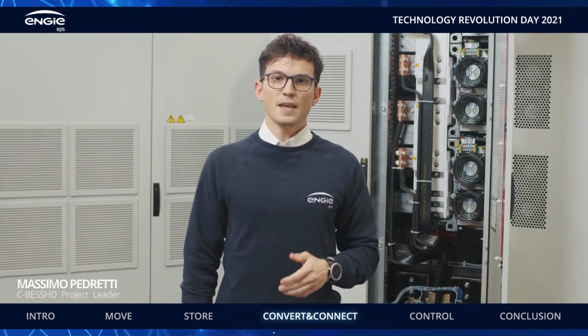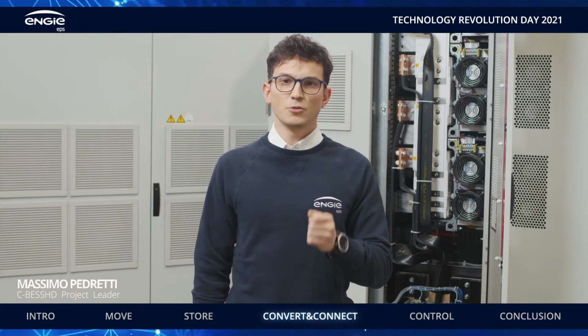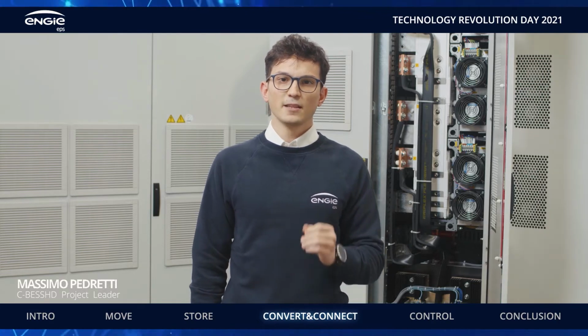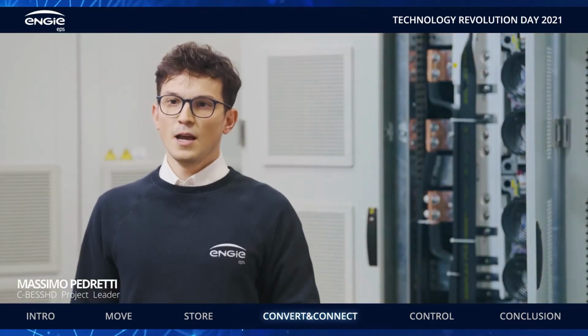C-BESS HD is a bidirectional power conversion system with complete circular capability. It is based on a modular 1500 VDC, 3-level NPC, IGBT-based power stack, and is available in 3 different configurations, from 1.1 to 1.8 MVA, with no thermal derating up to 45 degrees Celsius.